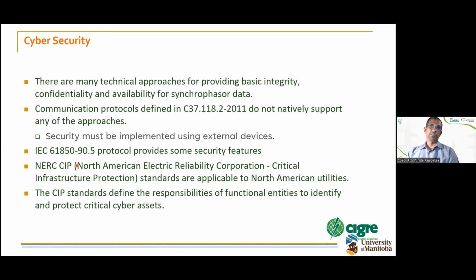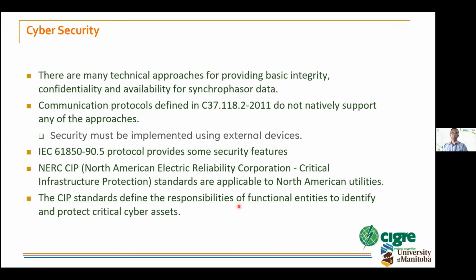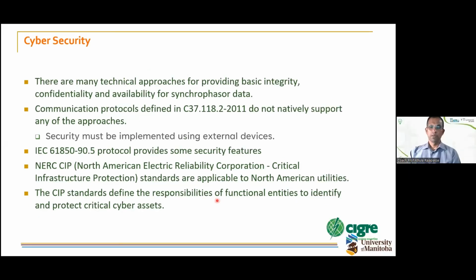But if we use the IEC 61850 90-5 protocol, it has certain inbuilt security features compared to this IEEE C37.118. In North America, there is something called the North American Electric Reliability Corporation, or NERC. It has certain standards on cybersecurity. All the North American utilities need to follow these cybersecurity standards. So the CIP, or critical infrastructure protection standards, are those applicable to cybersecurity, at least in North America.